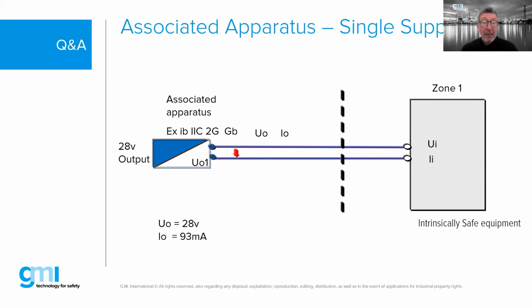If you don't put the barrier, then you can connect it to a 24-volt source, which you say is safe, but you don't know, because this 24-volt source may be powered by 250 volts, by connecting to a PLC, and eventually, on fault, this high voltage and high current can go down to the field.